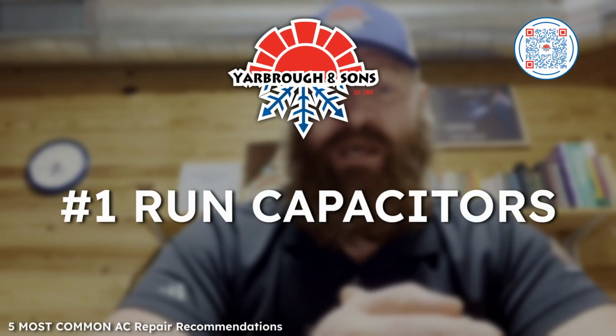Number 1, run capacitors. Run capacitors are probably the most common recommended repair that we offer on spring maintenances. We'll go out there and test that capacitor and see what it is. The manufacturer has a typical plus or minus 6 to 10% deviation for the rating of that run capacitor. If we see that your run capacitor is 10% or more out of specification per the capacitor manufacturer, we will recommend that as a repair during the maintenance.